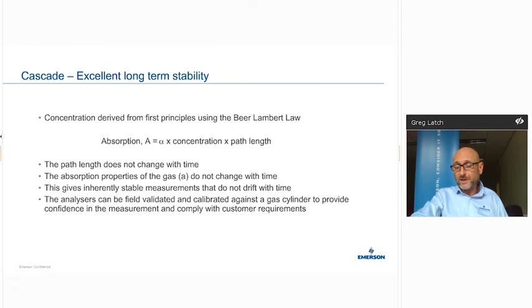With regard to the inherent stable measurements we have in this technology, and baselines based on linearity, etc, we're talking greater than 10 years in mean time between failures. It's absolutely exciting times moving ahead in this gas analysis space. In my eyes, this gives great confidence in the measurement and repeatability, depending on your application and requirements.